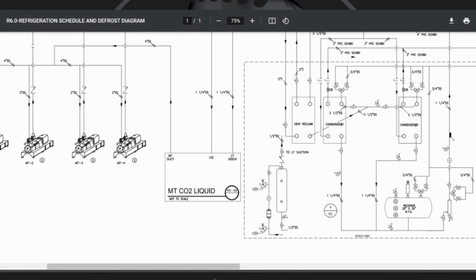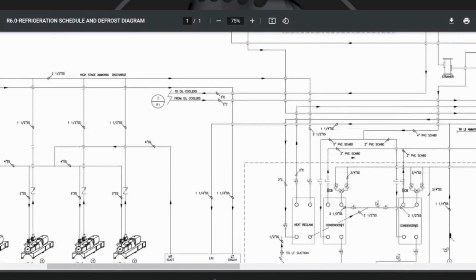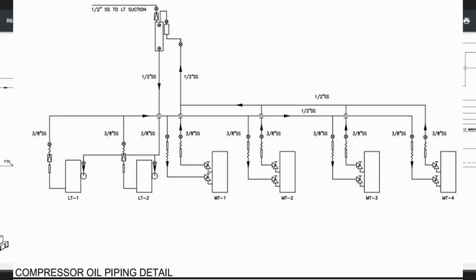overfeeds. Gotcha. Now, one thing you're going to notice here, anybody who's looking at this or hearing this, who's familiar with ammonia will immediately say, "Where's your oil separator?" And there is no oil separator on this system. Historically, we have been very opposed to oil separators. In our opinion, they're a crutch for poor design. There's really no need for them. But in this system, if I do another one, and when we do another one, we will probably put an oil separator in, but it really doesn't need it.